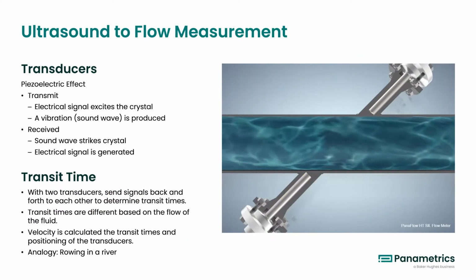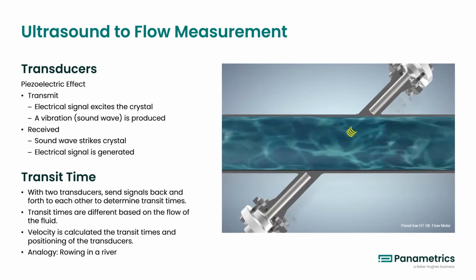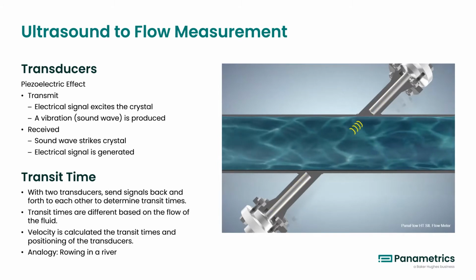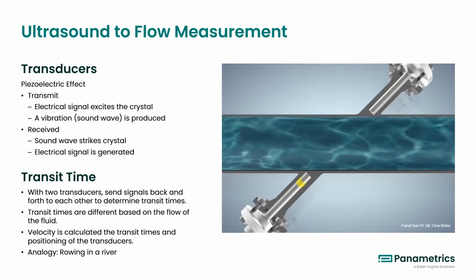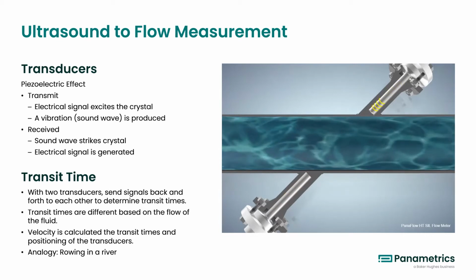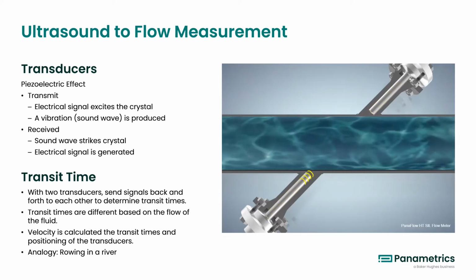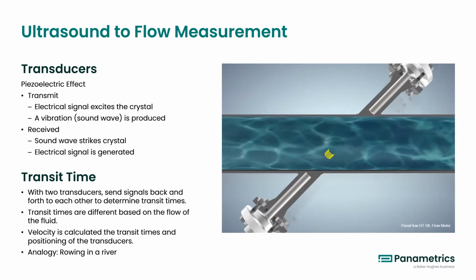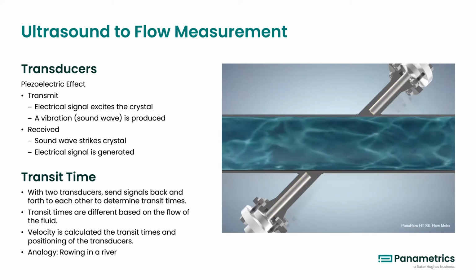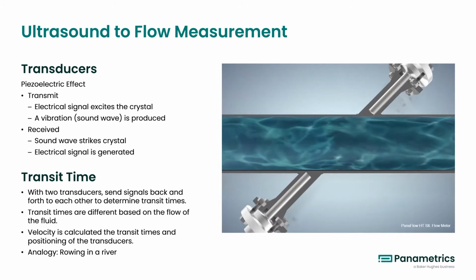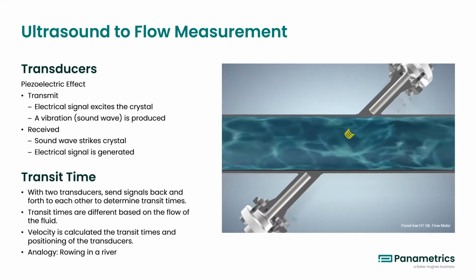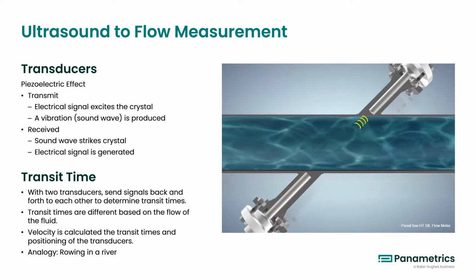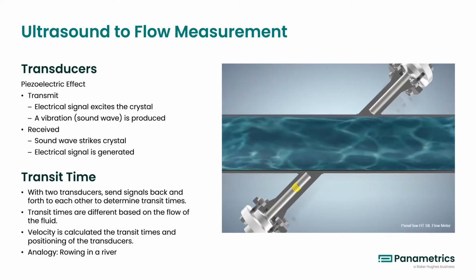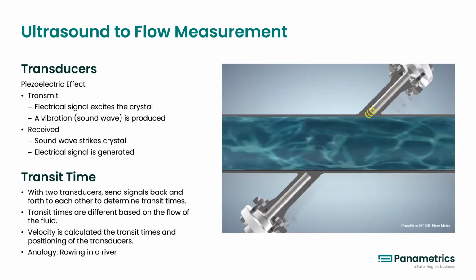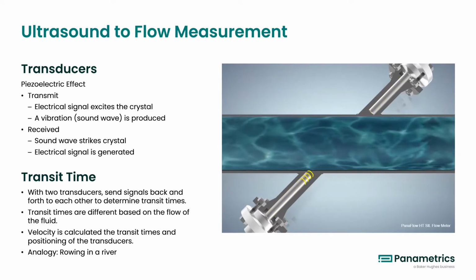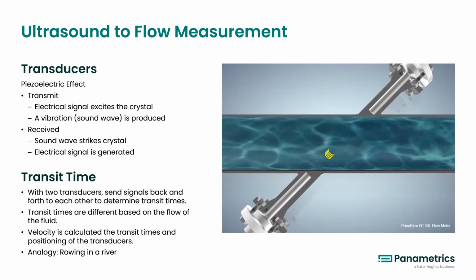The piezoelectric effect is the ability of certain materials to generate an electrical charge in response to an applied mechanical stress. Panametrics ultrasonic transducers use this phenomenon for signal creation and reception to generate and detect ultrasonic sound waves. The crystal generates sound waves when a voltage is applied to the material. The sound wave is created when the crystal deflects in response to the applied voltage. The crystal detects sound waves when the crystal deflects as the wave strikes the sensor. This deflection creates a voltage. The signals are sent and received into the process medium to detect the flow measurement, as shown by the animation.